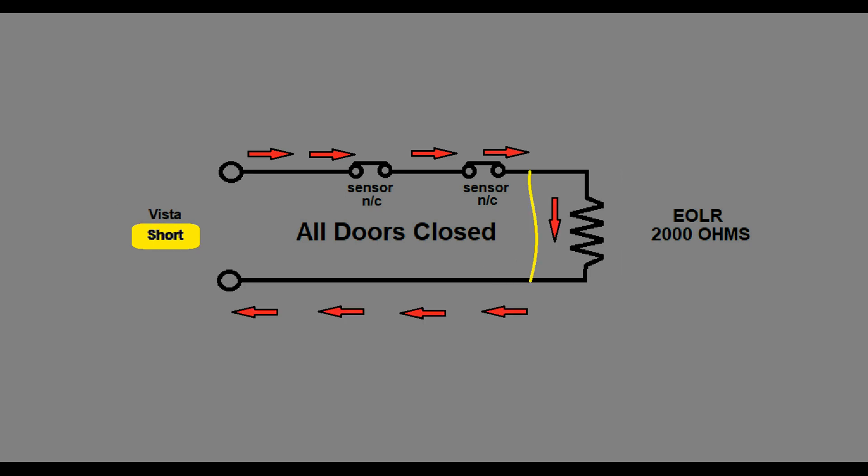Let's look at what happens with a short circuit. If there's a short across the end of line resistor, the current goes across the short, avoiding the resistor. The Vista panel will see the short and sound the trouble alarm.